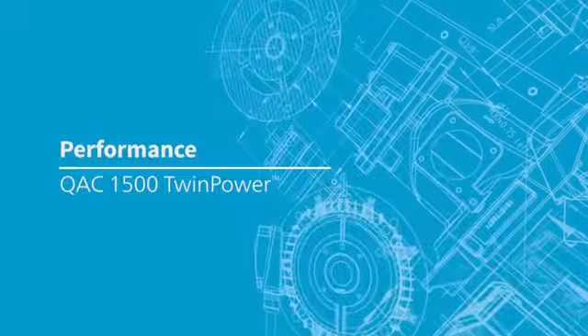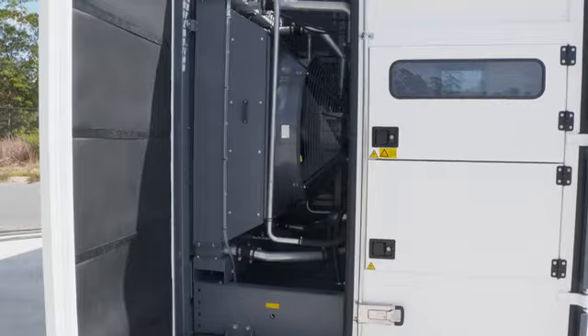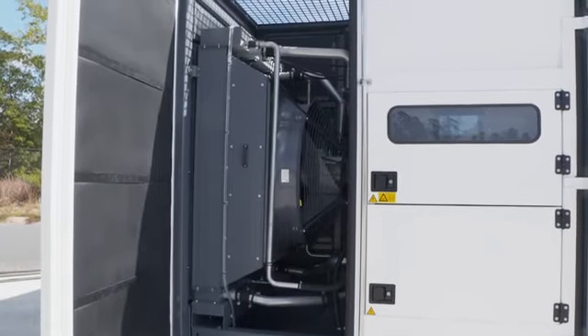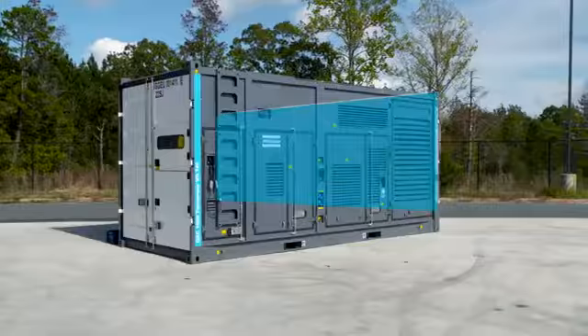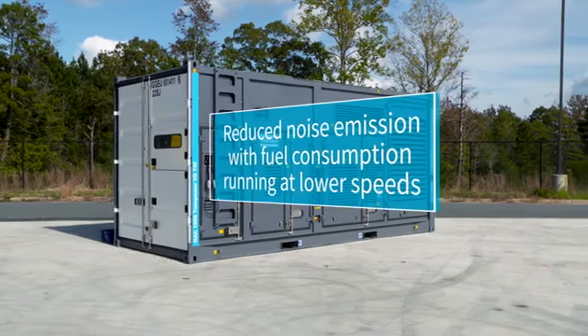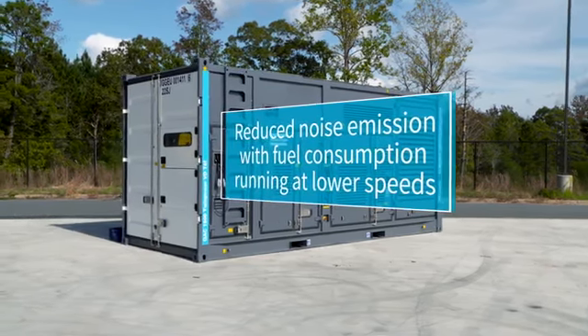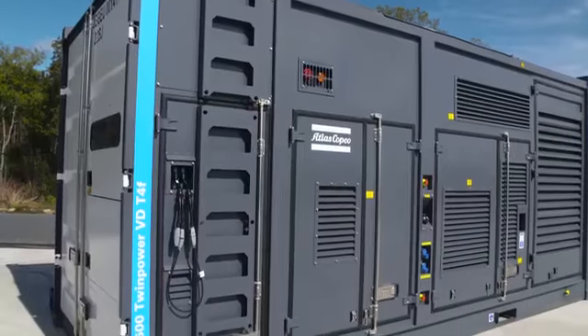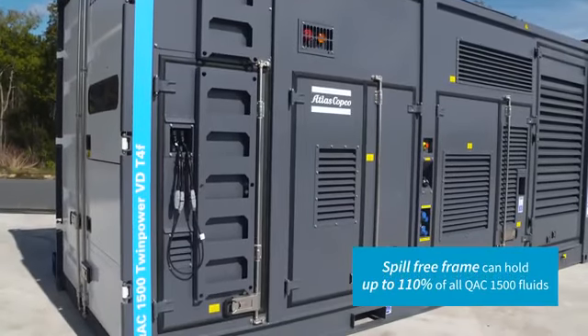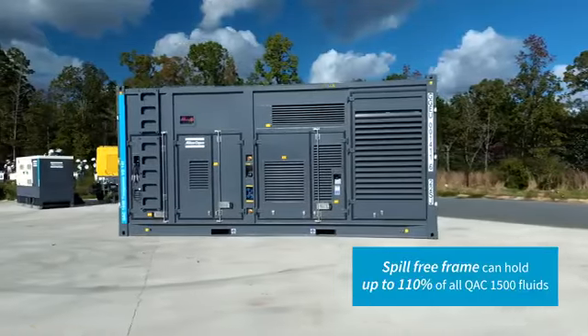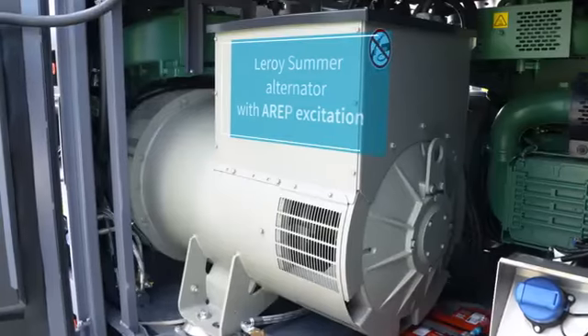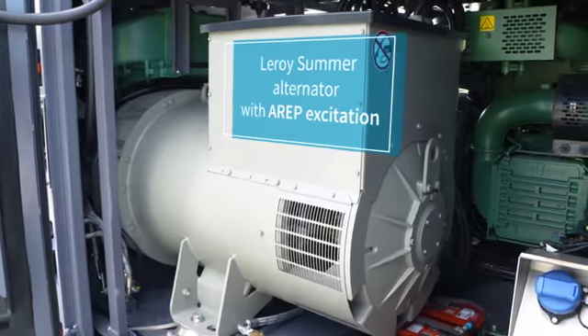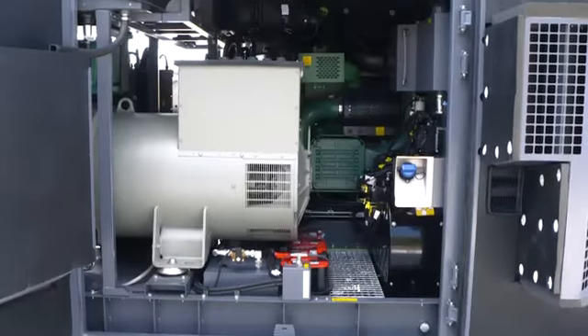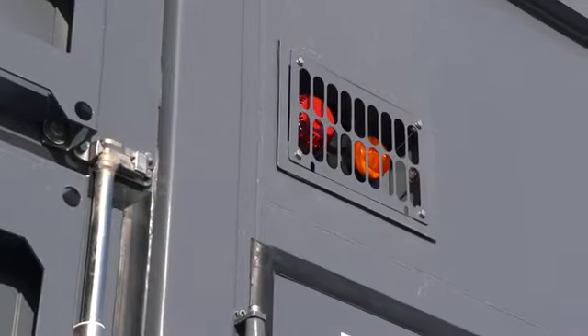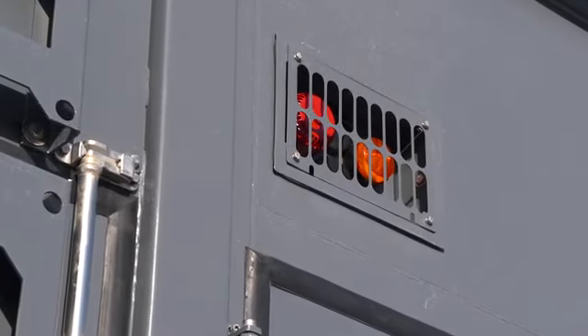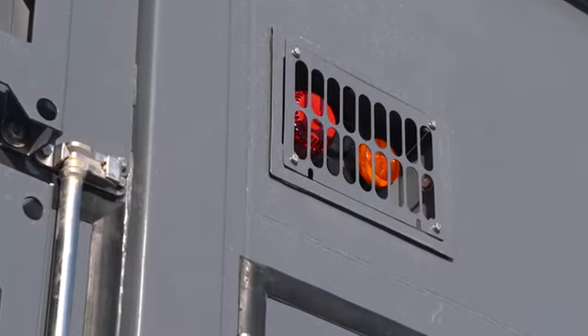Performance. The remote cooling system has a compact design with a highly efficient electro fan that is placed in a different compartment than the engine. This reduces noise emission, with fuel consumption running at lower speeds compared to the direct flow engine cooling systems. The spillage-free frame can contain up to 110% of all fluids of the QAC1500 generator. The Leroy Somer alternator includes the well-known AREP excitation, ideal for high-demand motor startup applications. The external alarm will promptly warn of any critical issues potentially affecting the performance of the generator.